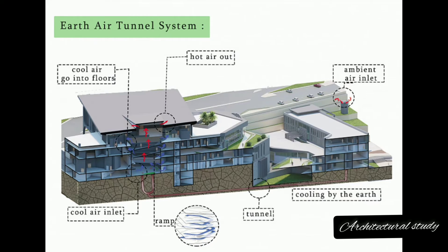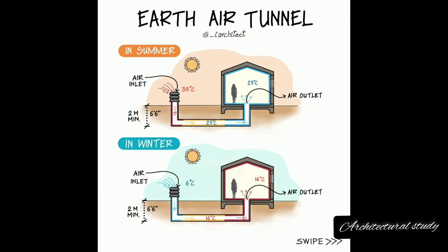Airflow: Required airflow depends on building size and desired cooling/heating capacity. Material of the Pipe: HDPE, PVC, and concrete are common choices, with varying cost, durability, and thermal conductivity considerations. Duct Layout: Open-loop systems offer high heat exchange but require air filtration, while closed-loop systems provide cleaner air but may need longer pipes. Spiral and vertical configurations are also employed.